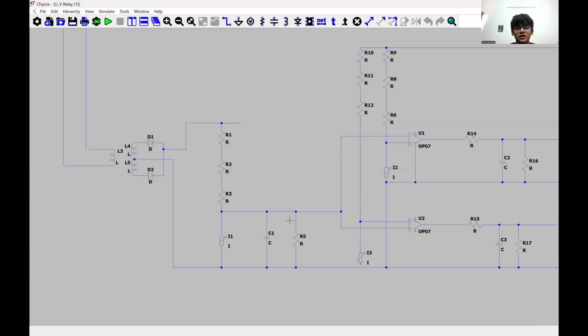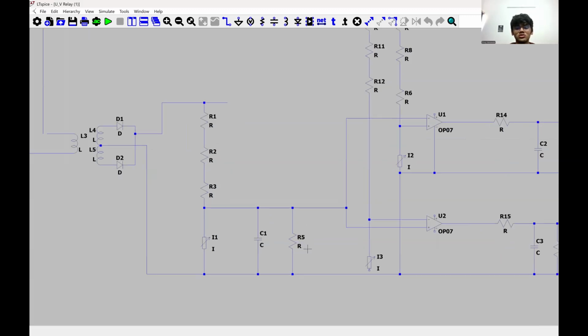We faced a trade-off: a lower resistance allows for a fast, safe discharge but introduces high voltage ripples, while a higher resistance stabilizes the DC signal but takes too long to discharge. We had to balance this to ensure the circuit remains responsive during a fault. This 18-volt filtered output now serves as the input for our comparator and under-voltage detection logic.